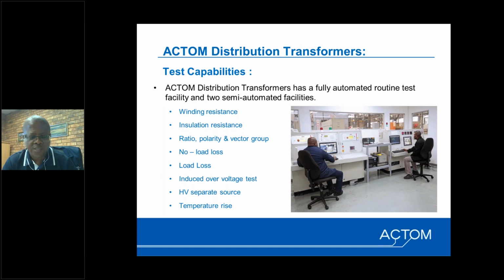On the right, the panel is semi-automated. The CTs, VTs, the selection is still manual, but everything else, data capture, is also automated. We do conduct full routine tests on these 2 test systems, and we can also conduct a temperature rise. But these are only up to 2.5 MVA. The bigger units are done in our high bay.